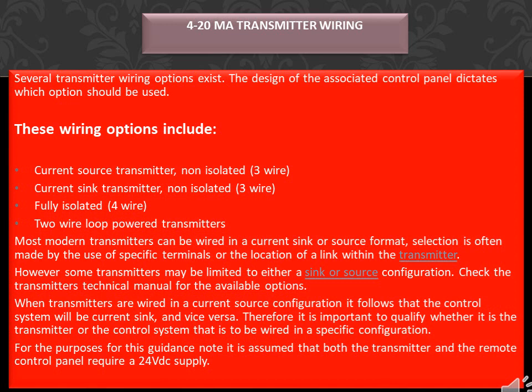However, some transmitters may be limited to either a sink or source configuration. Check the transmitter's technical manual for the available options. When transmitters are wired in a current source configuration, it follows that the control system will be current sink, and vice versa. Therefore it is important to qualify whether it is the transmitter or the control system that is to be wired in a specific configuration. For the purposes of this guidance note, it is assumed that both the transmitter and the remote control panel require a 24VDC supply.